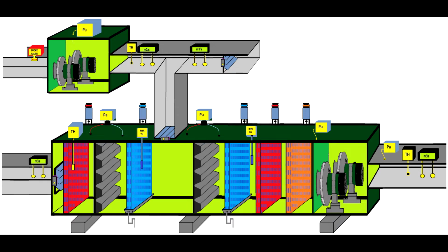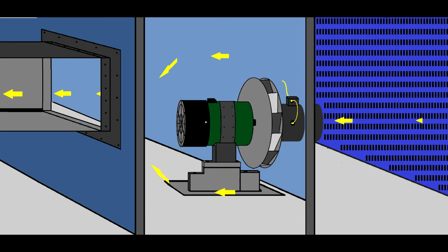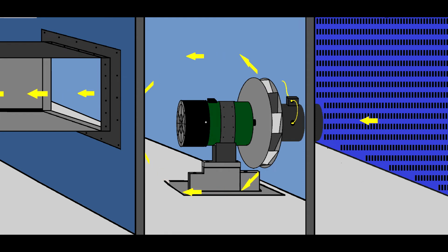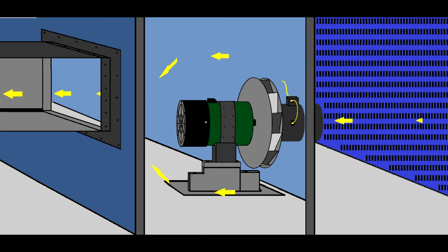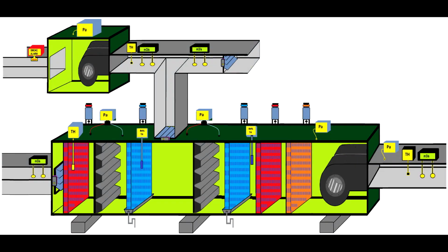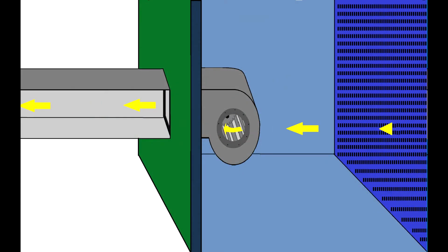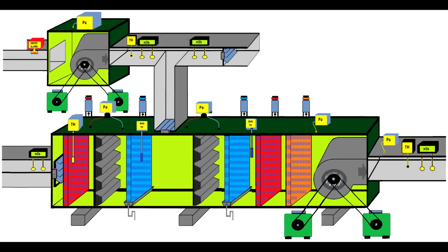Now you end up with a fully functional air handling unit. It's using this axial fan, and like I told you before, this axial fan is great. It gives you a complete electrical and mechanical redundancy. You can use a scroll fan, which will give you a complete redundancy if you know how to design it. Bear in mind, each of these fans must have the capability to provide the amount of air on its own. You can use belt-driven fans. Now, I want to talk more about the belt-driven fans.